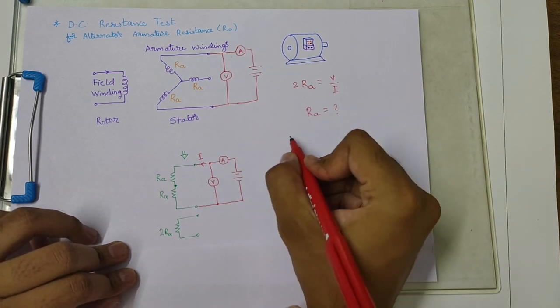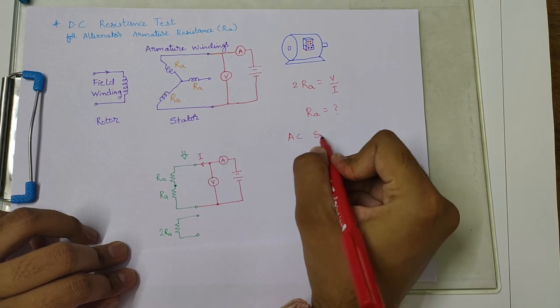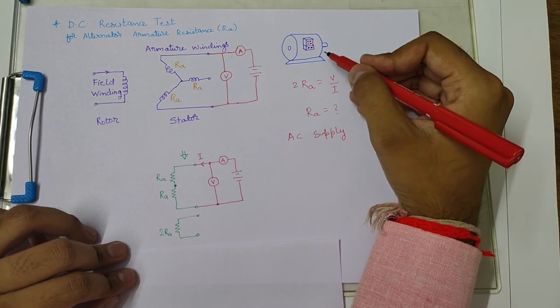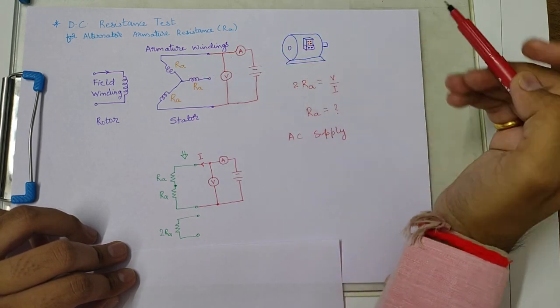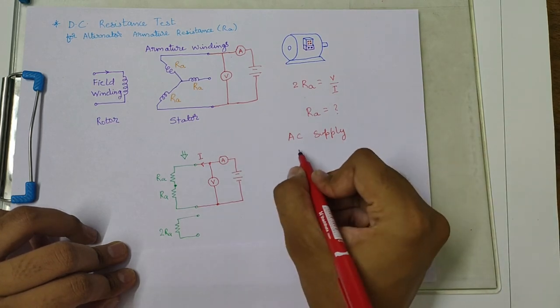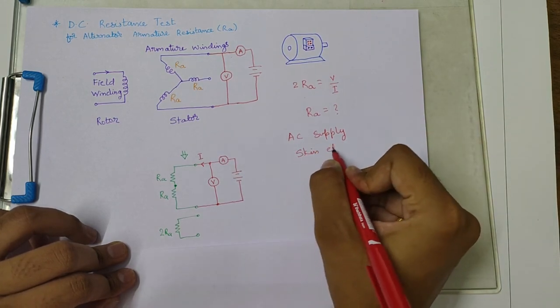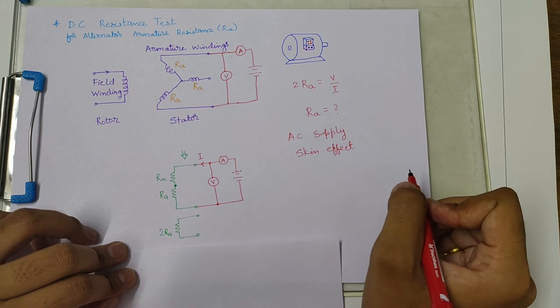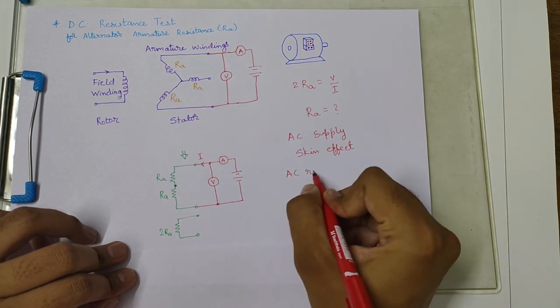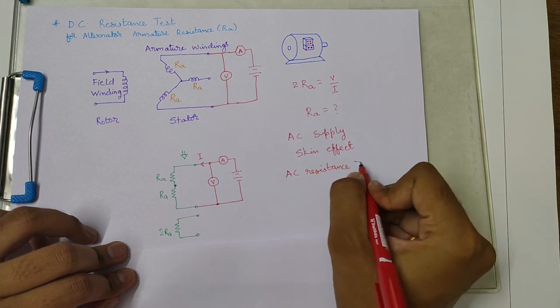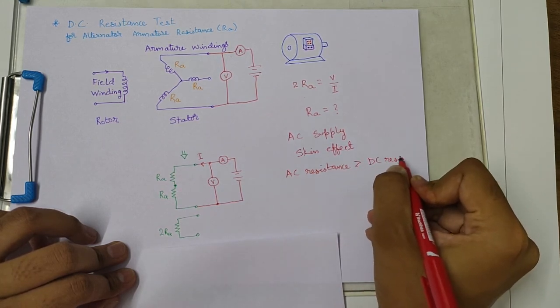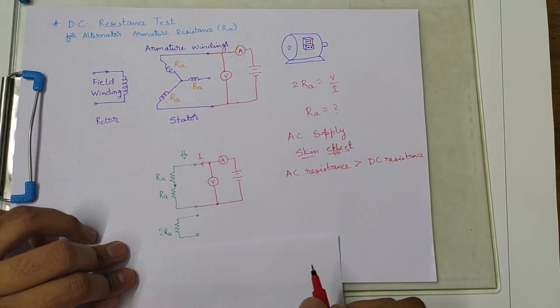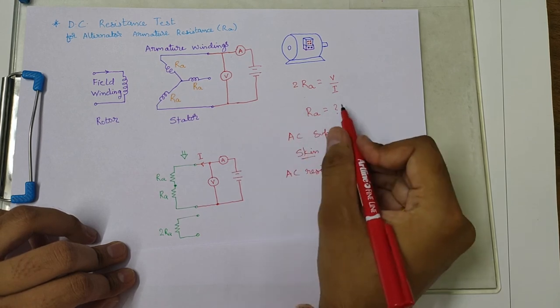Now it is important to note here that this is a DC resistance test. When we give AC supply to the alternator, when this alternator will be generating alternating current, alternating current will be flowing through the windings, and so the resistance in AC condition changes because of the skin effect. So AC resistance is always greater than DC resistance because of skin effect.